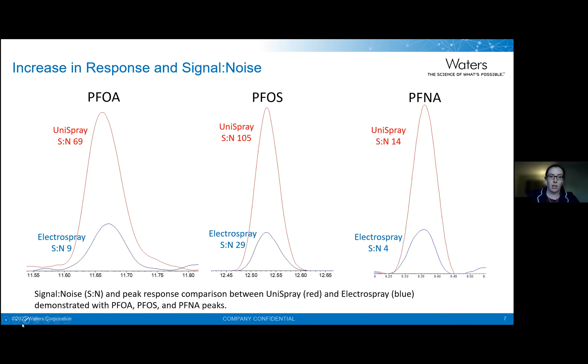And that increase in signal to noise is pretty reproducible across the different traditional targeted PFAS compounds. PFBA, for instance, we see quite an increase in the signal to noise value compared to electrospray. In this graph, 1 would be the same signal to noise for the Unispray to electrospray. And for the ones we really see, we see comparable or better signal to noise with the Unispray source. So that's really exciting.